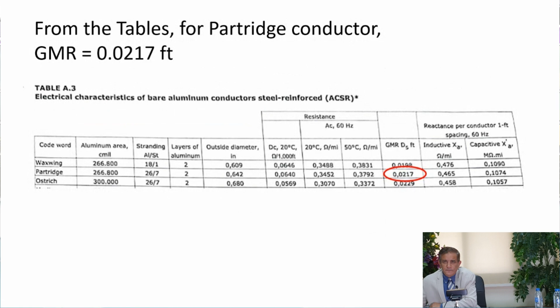For this partridge conductor, you can see here in the table, the GMR is 0.0217. So you can calculate both XA and XD. Once you get this, it will be in ohm per mile, both XA and XD. It's only the same equation, the same formula we used before.